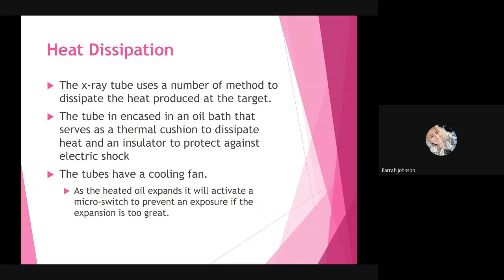Then that brings us to heat dissipation. Know that X-ray tubes get very, very hot. We are consistently creating tons of thermionic emissions, so we have to have a way to dissipate that constant heat production. The X-ray tube uses a number of methods to dissipate the heat produced at the target. The tube is encased in an oil bath that serves as a thermal cushion to dissipate heat and an insulator to protect against electric shock.